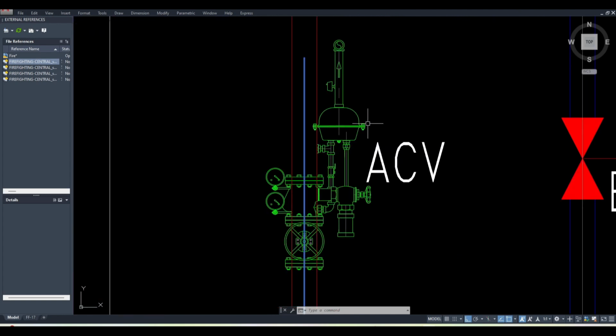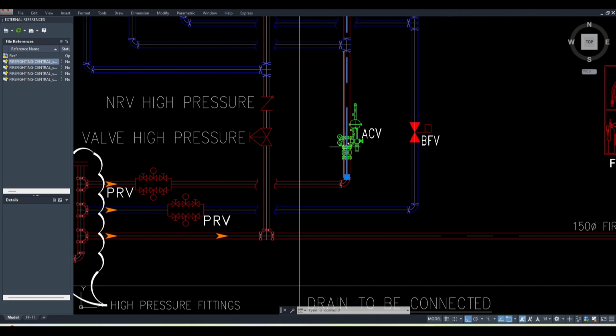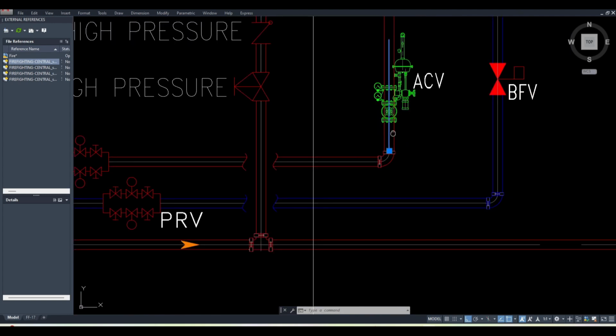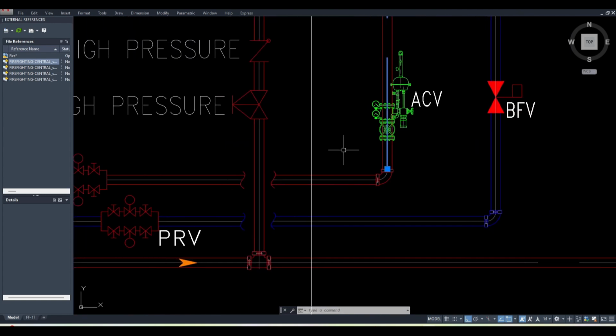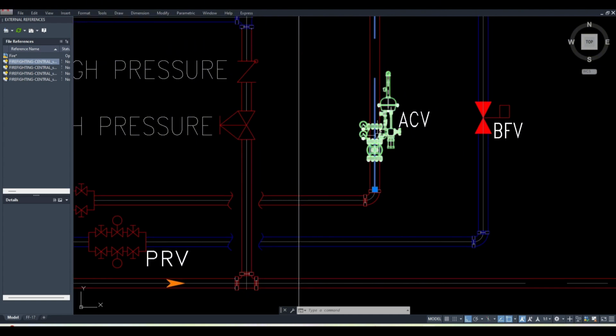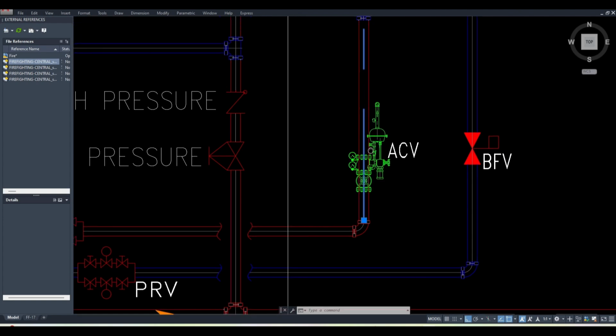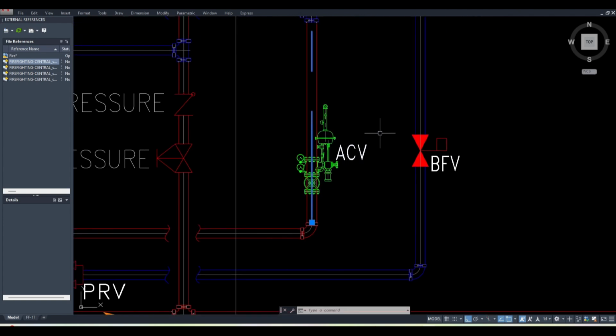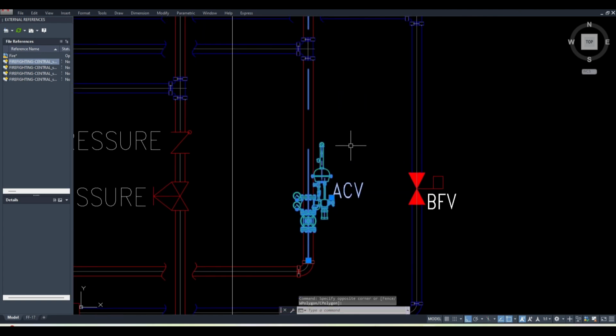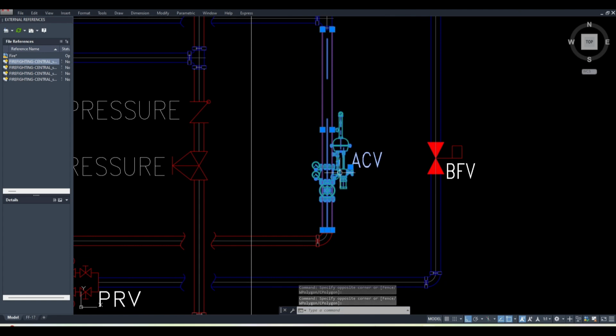Also, there is a surge protection here. So suppose because of the up and down, or a sudden surge in the pressure, of course that also it can handle here for the false alarm, like in a false condition it will not allow the system to break, okay. So all these things it does, one alarm check valve. That's why in each riser we keep one alarm check valve, okay.